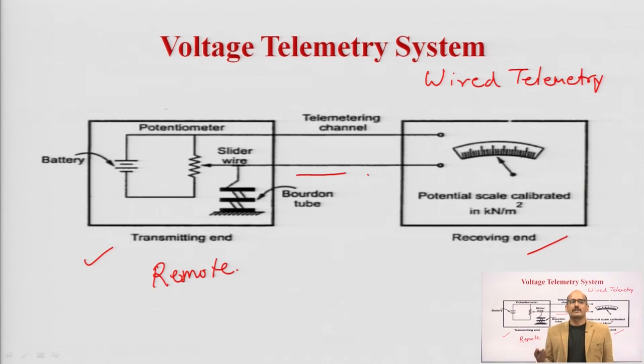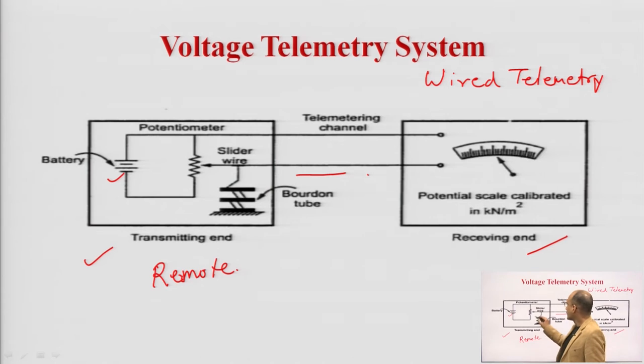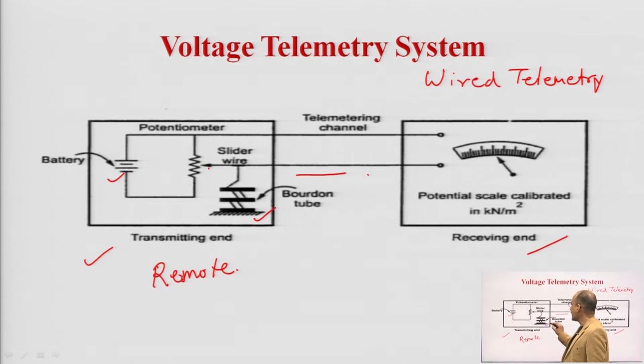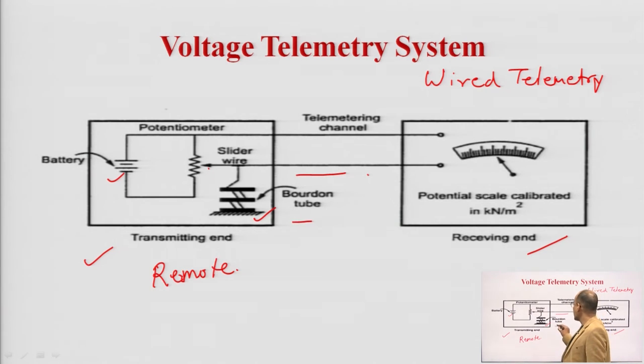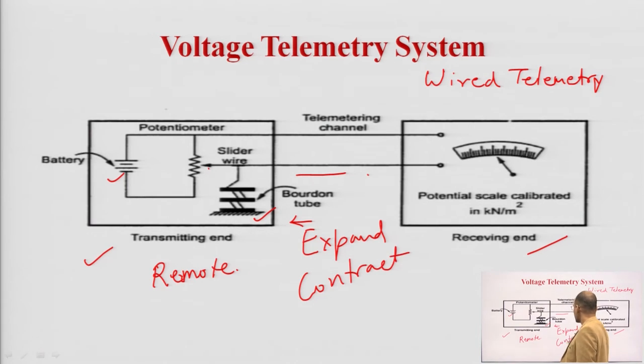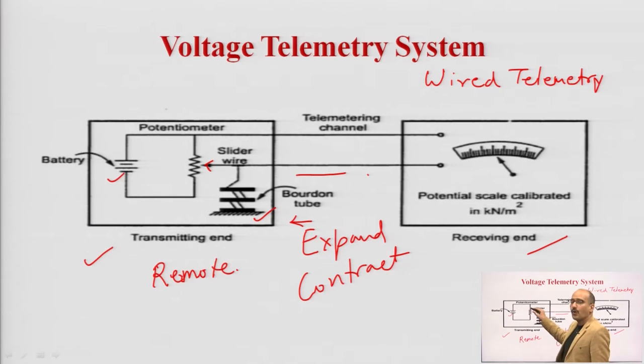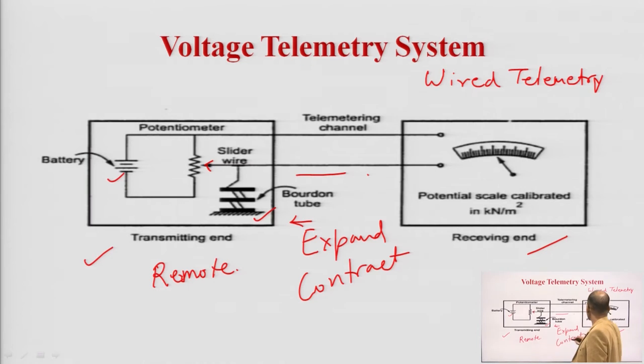In the voltage telemetry system arrangement, you can see a battery and a potentiometer arrangement with a slide wire connected in series. A Bourdon tube is applied here, made of elastic material. When pressure is applied on the Bourdon tube, it will either expand or contract. When it expands or contracts, it changes the position of the slide wire. Due to this change in the slide wire, the overall resistance of the potentiometer will change. That change in potentiometer resistance is measured through the potential scale, which is connected in parallel.